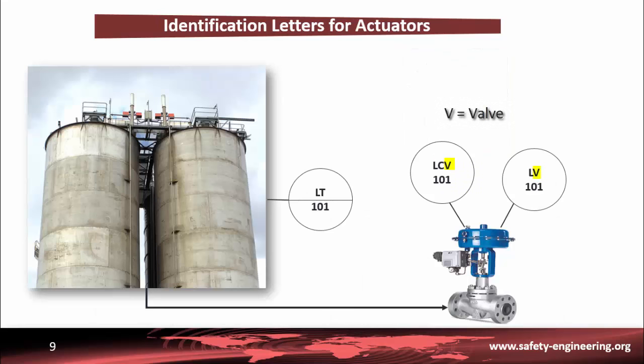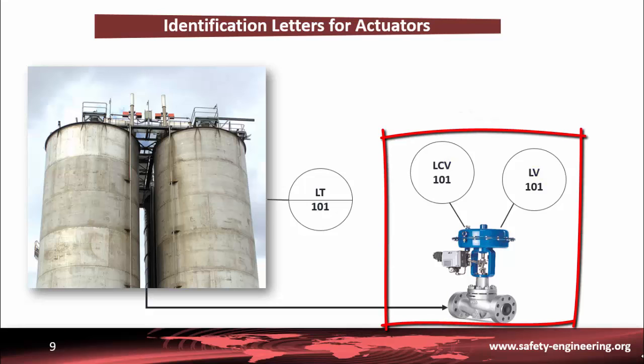When the second or third letter is V, the associated device is a valve. A valve is an actuator — a part of a final control device that causes a physical change. For example, LV or LCV (for control valve) means a valve to adjust the flow rate in order to control the level.